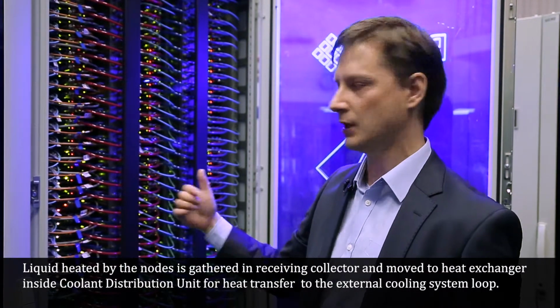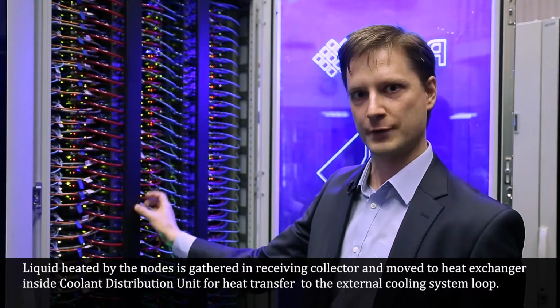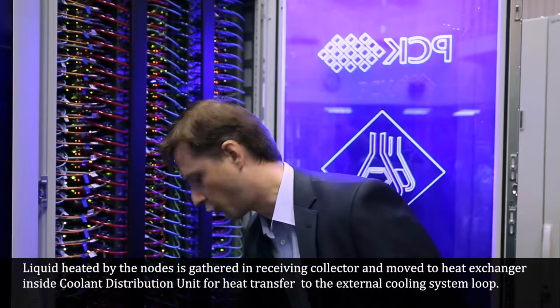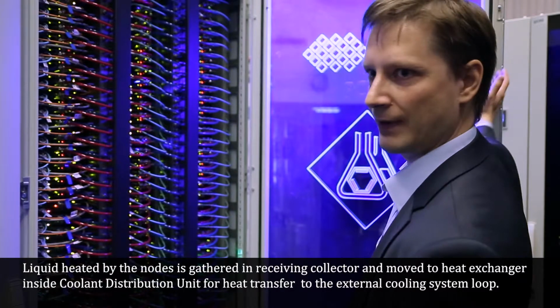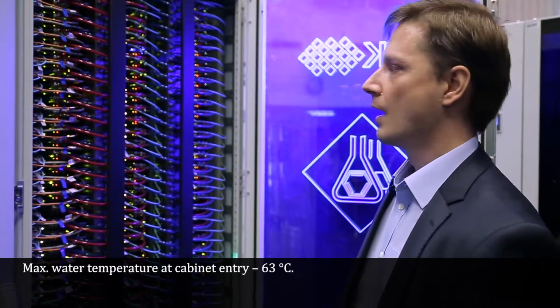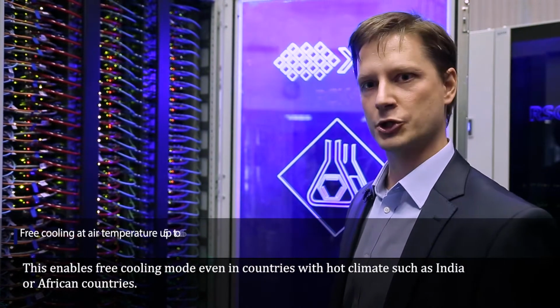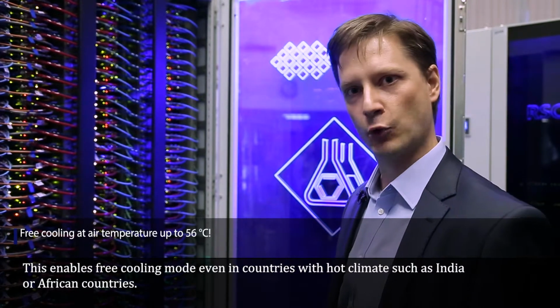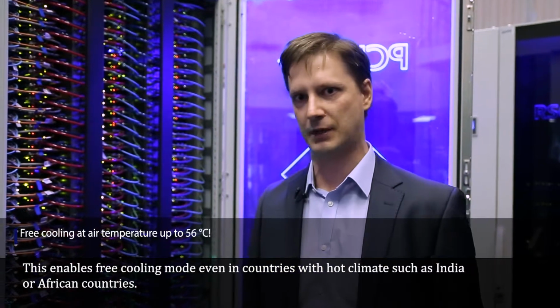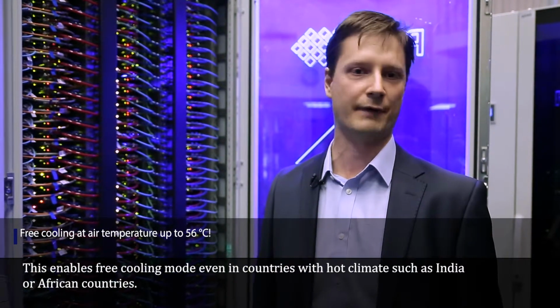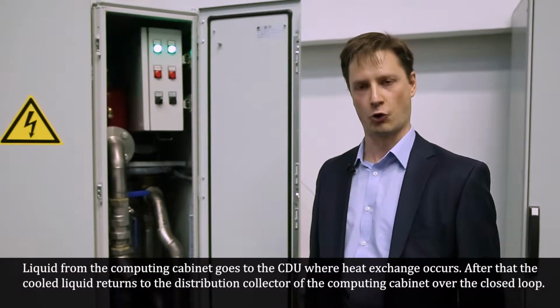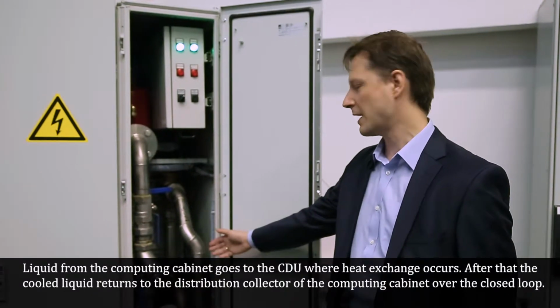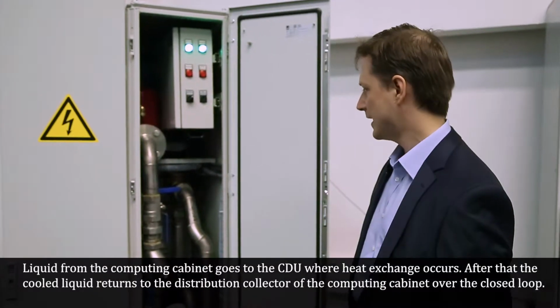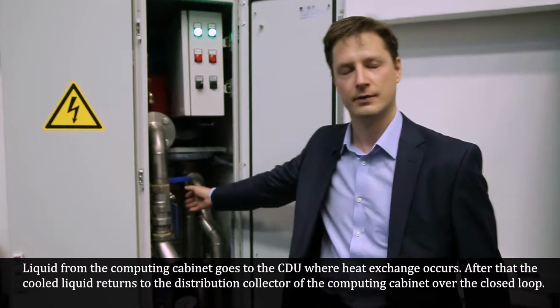Liquid heated by the nodes is gathered in the receiving collector and moved to the heat exchanger inside the coolant distribution unit for heat transfer to the external cooling system loop. Maximum water temperature at cabinet entry is 63 degrees Celsius. This enables free cooling mode, even in countries with a hot climate, such as India or African countries. Liquid from the computing cabinet goes to the CDU, where heat exchange occurs. After that, the cooled liquid returns to the distribution collector of the computing cabinet over the closed loop.